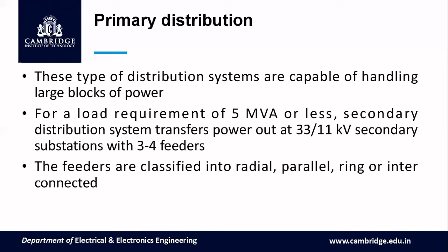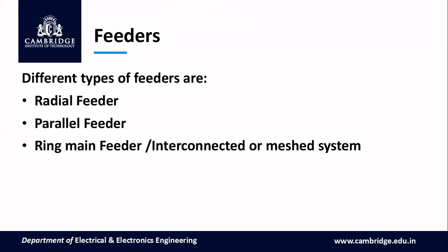Here, again they may be classified into primary distribution and secondary distribution. In the primary distribution, we saw 66 kV to 33 or 3.3 kV. In the secondary distribution, the 33 or 11 kV will again be stepped down to 3.3 or 6.6 kilovolt, which will be distributed with the help of 3 to 4 feeders. The feeders may be radial, parallel, ring, or interconnected or meshed systems. So the different types of feeders available are radial, parallel, ring main or interconnected.